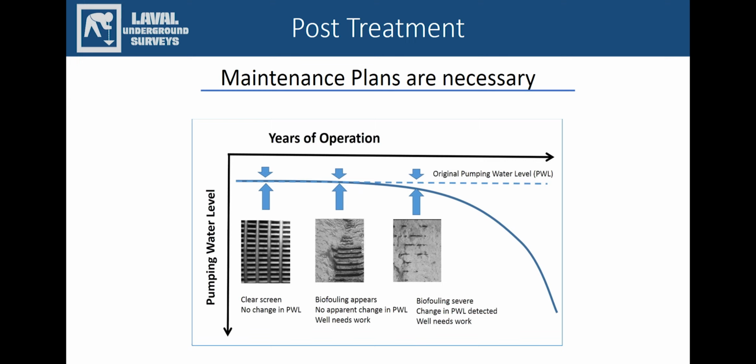The best way to get ahead of this is to regularly clean the well. It depends on how big the issue is in each area. Some areas need to be checked and maintained every 8 months, some need it only every 2 years. That's why it's a good idea to get water samples and to have visual verification every once in a while just to stay on top of those issues.